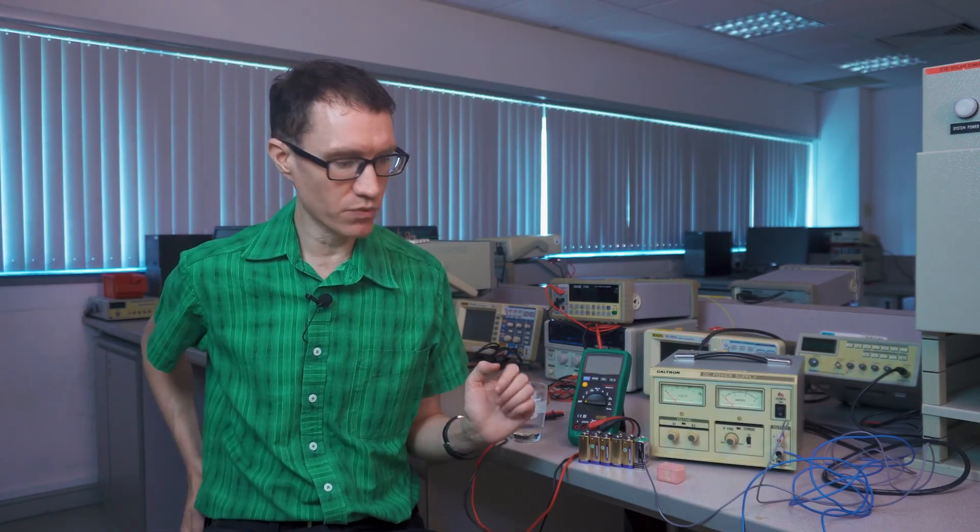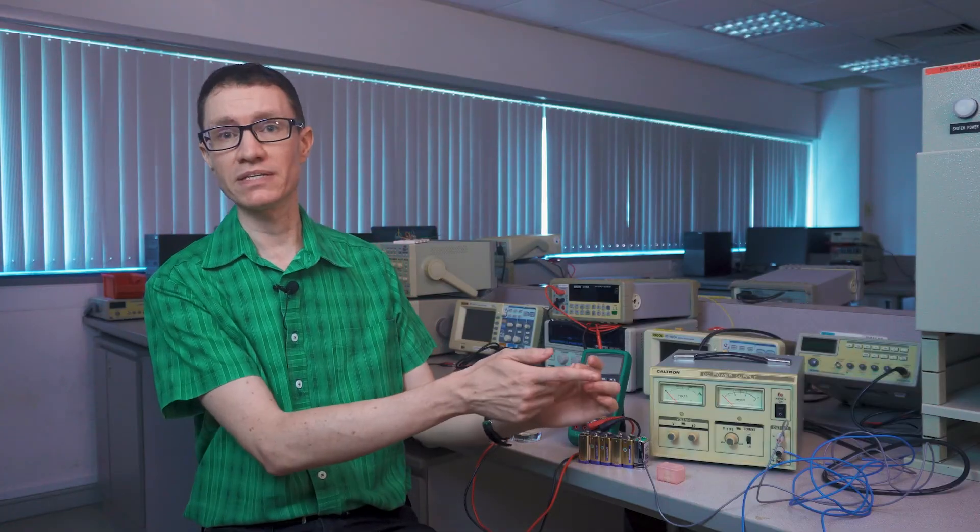The second tip I have when working around electricity is to only use one hand as much as possible. You might have noticed that when I was doing the experiment here with the DC power supply, I was only using one hand. I kept my other hand safely away from the experiment in my pocket. Of course, the reason is that I didn't want to accidentally touch ground or another conductor that could have potentially sent a fatal current through my body. Right now, I'm isolated from the ground by sitting on a stool that has thick rubber feet and I'm wearing shoes with thick rubber soles. The reason for that is to prevent my body from accidentally being grounded, which could be dangerous in situations of high voltage.